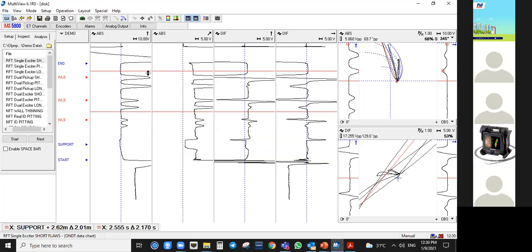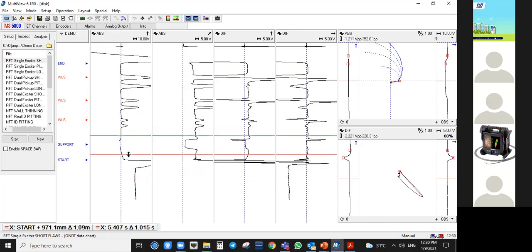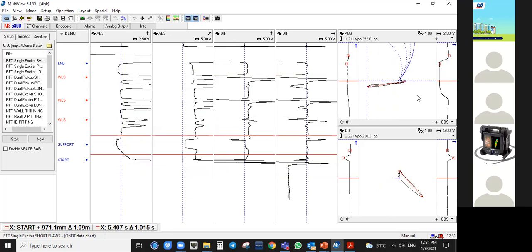Once you do that, you must also rotate your support. You must rotate to a point where this is the indication that you have a support. If you see the indication go back to 0, that means there's no flow of magnetic field. That means there's a support blocking the magnetic field. So it will go back to 0 and then go back again to the standard thickness of the material.